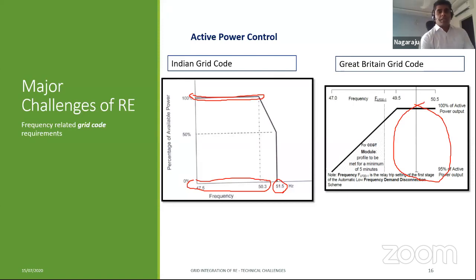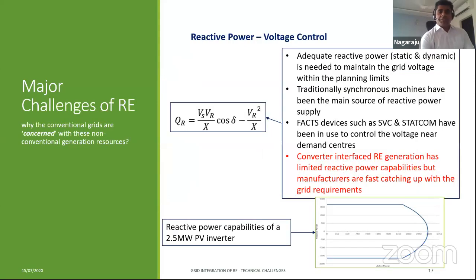Okay, so then that is the requirement from the grid codes. So the next challenge we talked about was the reactive power. Again, I'm trying to show you some of the fundamental equations, reactive power and voltage interdependencies. Adequate reactive power is needed to maintain the grid voltage. Traditionally, synchronous machines have been providing that, and lately, in the last few decades, flexible AC transmission devices such as SVC and STATCOM have been helping the grids to provide that.